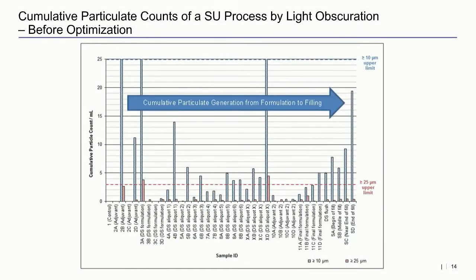So you can see in this graph we show this is before optimization, and this is the cumulative particle counts, and at the bottom you see all the samples themselves that we took at the various stages that were noted in the flow diagram 2 slides earlier. So you can see on the right the greater than or equal to 10 microns and greater than or equal to 25 microns and the limits of the particle counts there. So after the initial pre-optimized process, the counts were a little higher than expected in 3 main areas of the process.